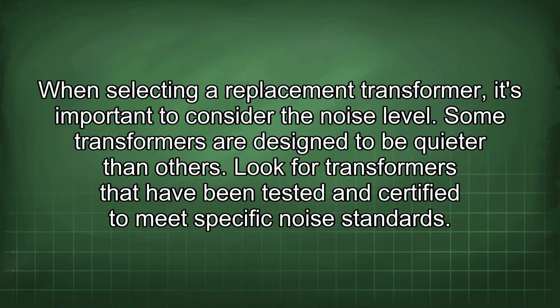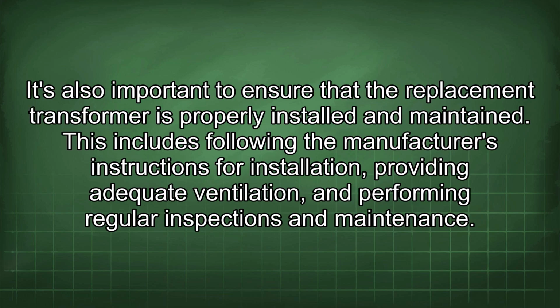When selecting a replacement transformer, it's important to consider the noise level. Some transformers are designed to be quieter than others. Look for transformers that have been tested and certified to meet specific noise standards. It's also important to ensure that the replacement transformer is properly installed and maintained. This includes following the manufacturer's instructions for installation, providing adequate ventilation, and performing regular inspections and maintenance.